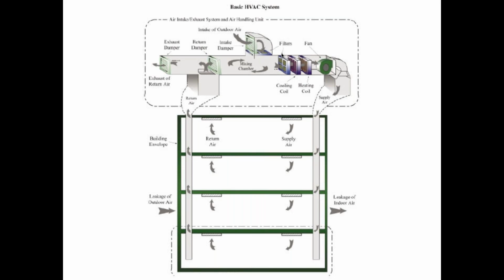But that gives us an opportunity to condition the air, to let the unit know that we're cold in here, which means heat up the air, or we're hot in here, cool off the air. So in order to do that, if you look here, that's called a perimeter unit. We'll get to that in a little while. That's supplemental heating and cooling, right? So in other words, we've got one system here and we've got another system that's over there underneath those windows. Okay, so we have two ways that they heat and cool this space, right?